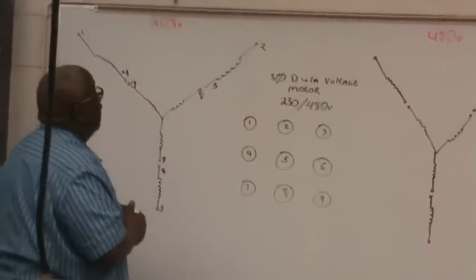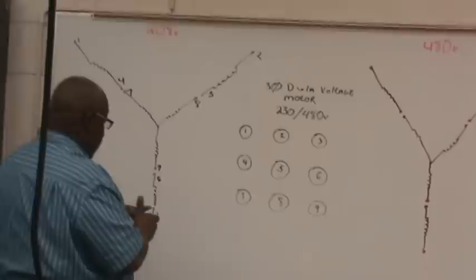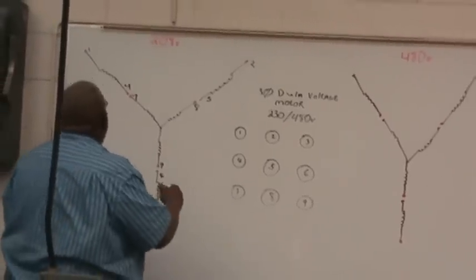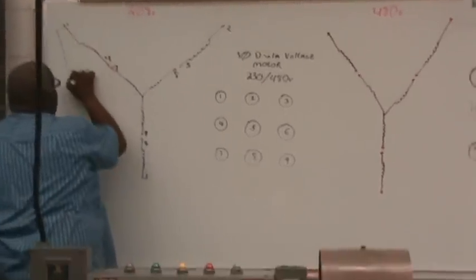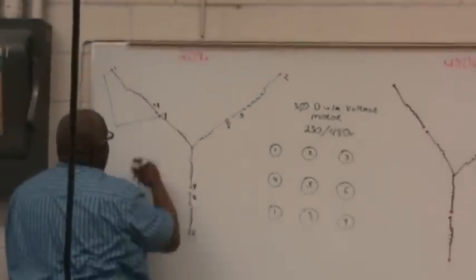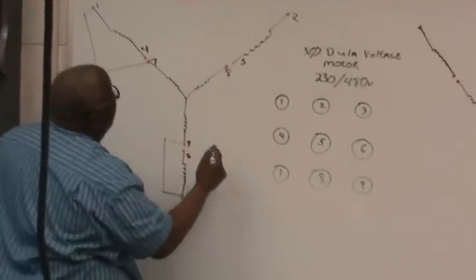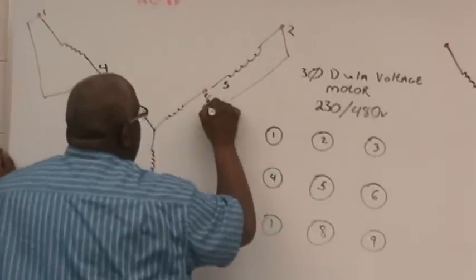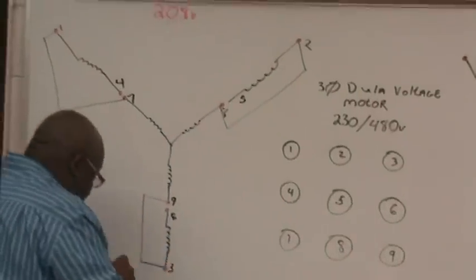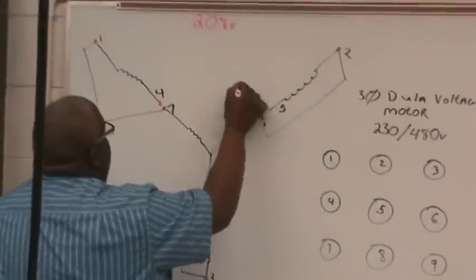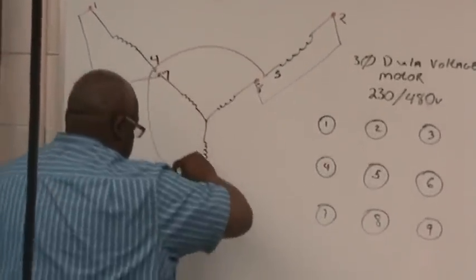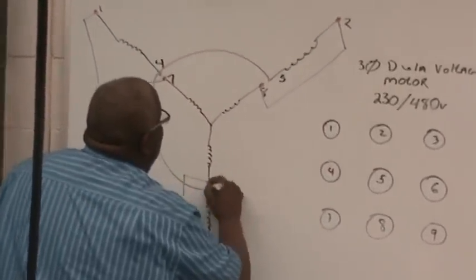How to configure for a low voltage motor: you do one to seven, and you tie three to nine, and you tie two to eight. Four, five, and six, you tie together.